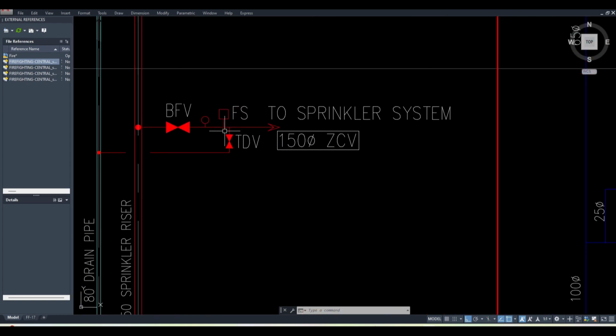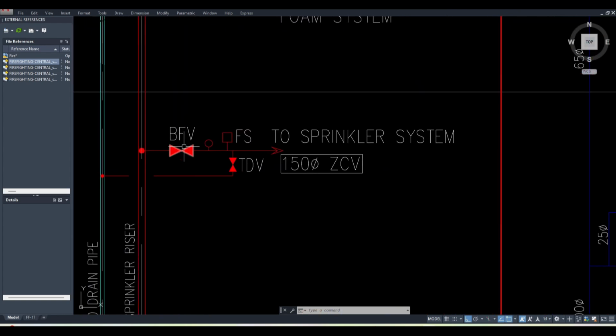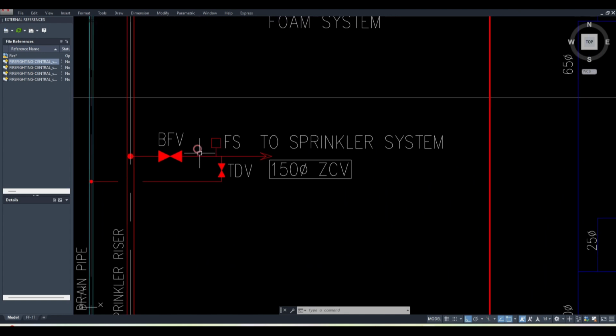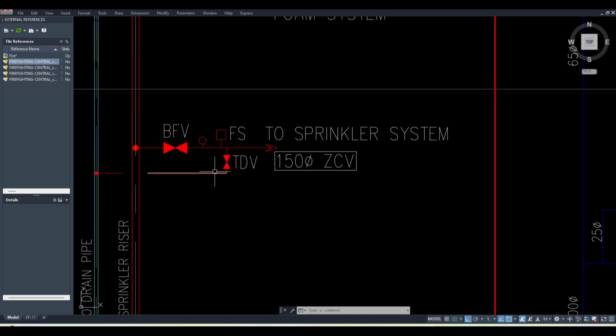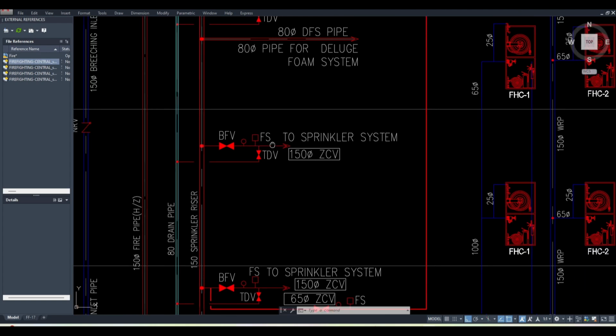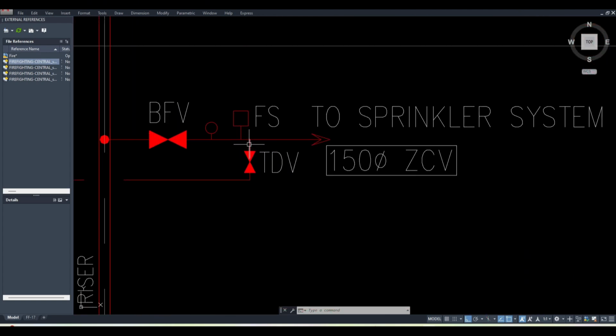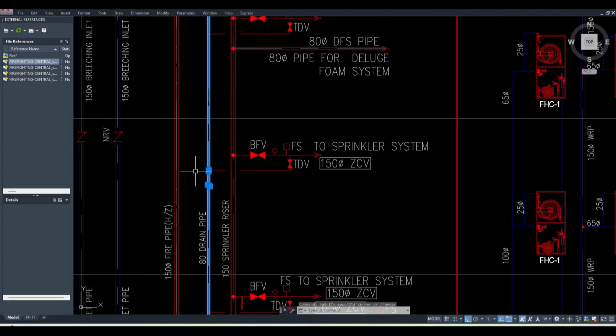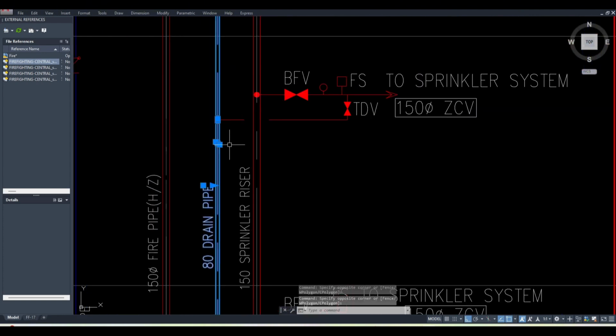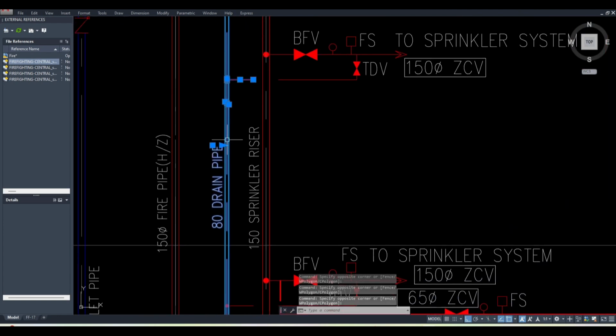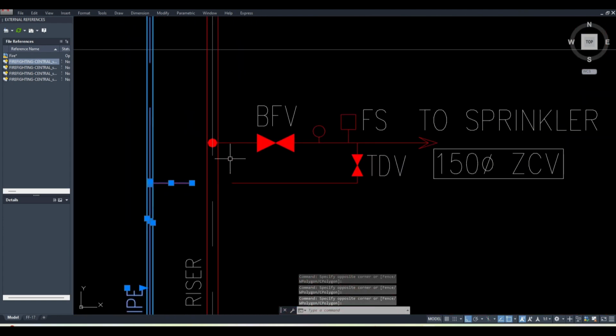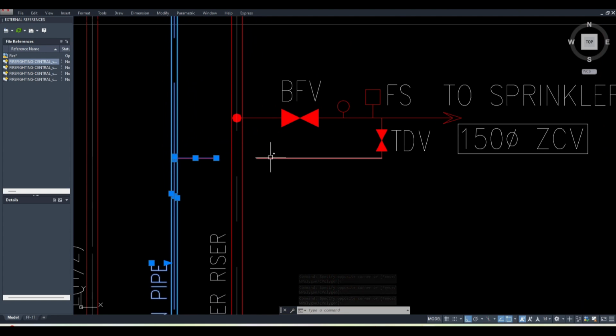So zone control valve is nothing but the combination of butterfly valve, then flow switch, pressure gauge, and then there is a drain point here. So in case of maintenance, what we do is we drain this pipe out, the water, and then it goes to the same. You remember yesterday I told you that there should be a drain pipe which should not be less than 3 inches, which is 80 mm here.